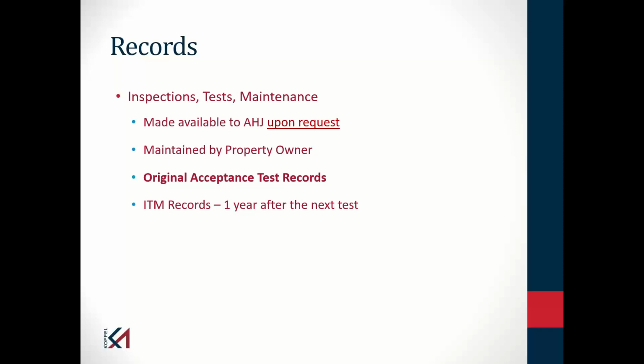And the reason for that is some of these tests are comparative tests. I want to see if the pressure is decreasing over a period of time, or the flow in the fire pump is decreasing over a period of time. Now, I bolded that third bullet because NFPA 25 also says that you are to maintain the original acceptance test records.